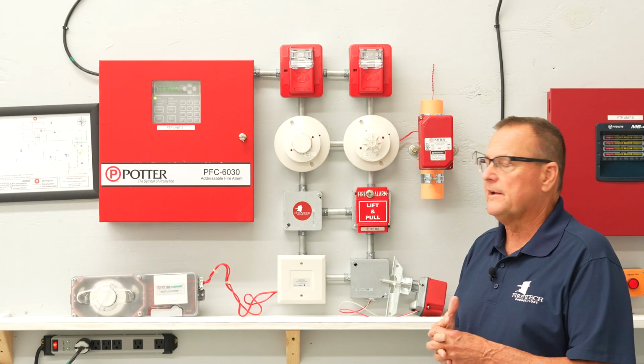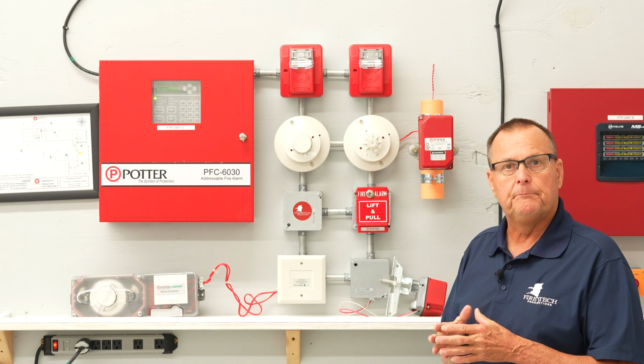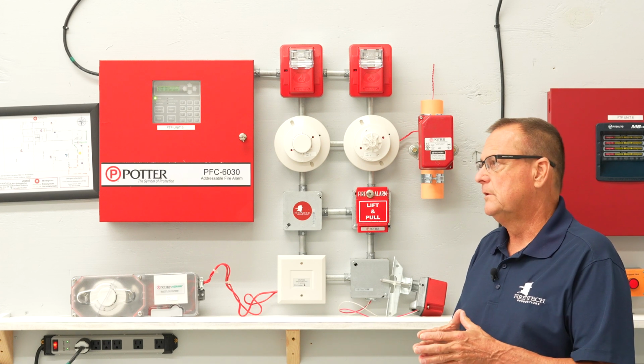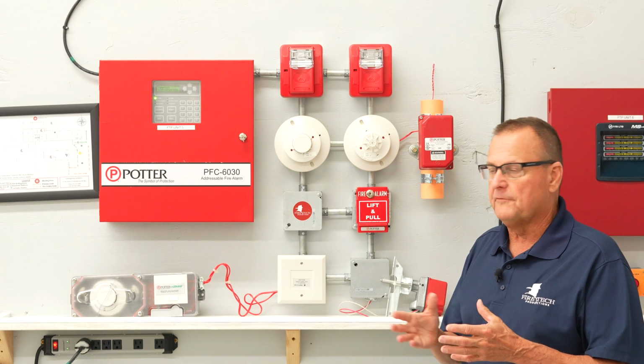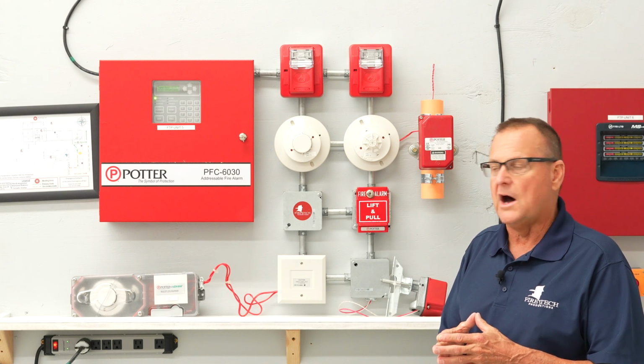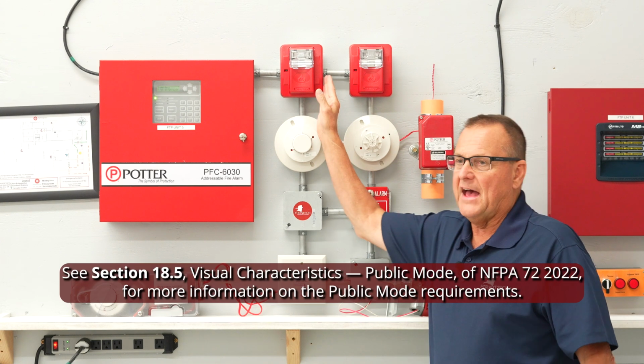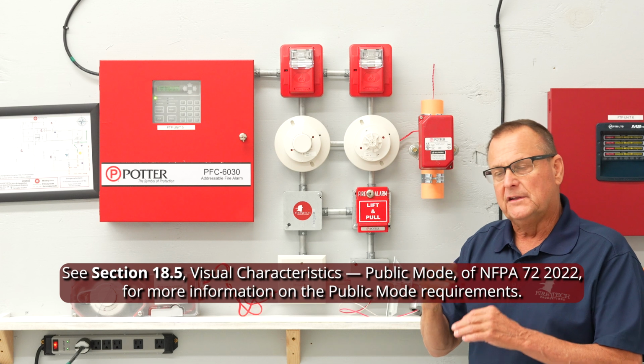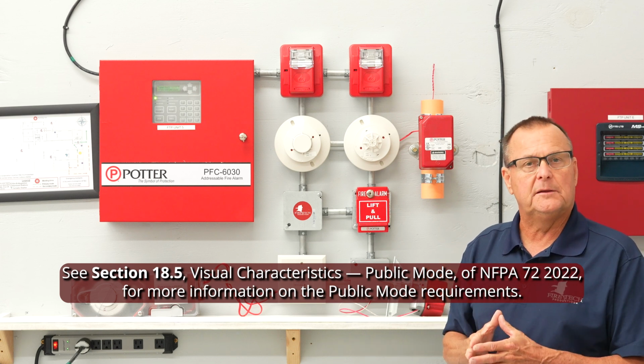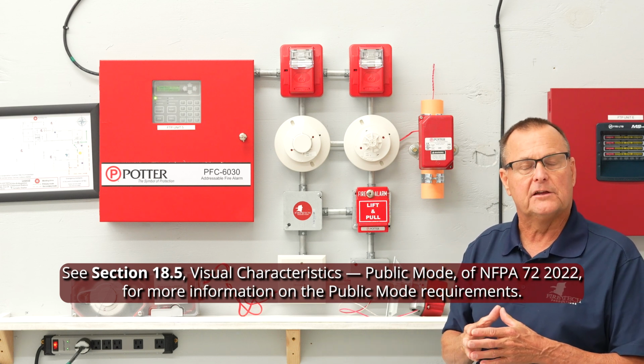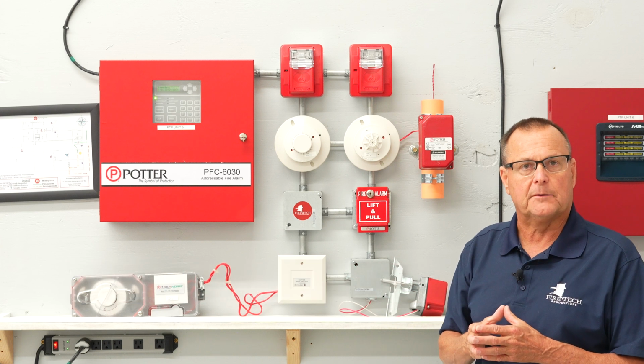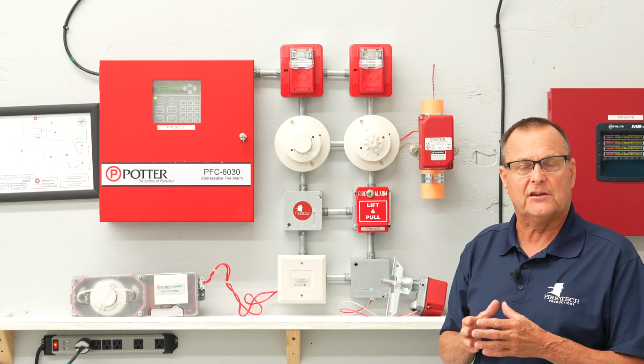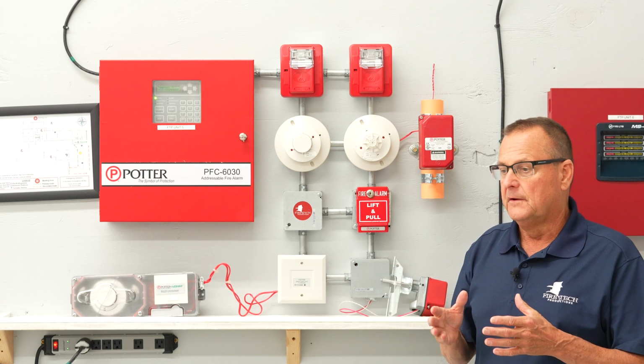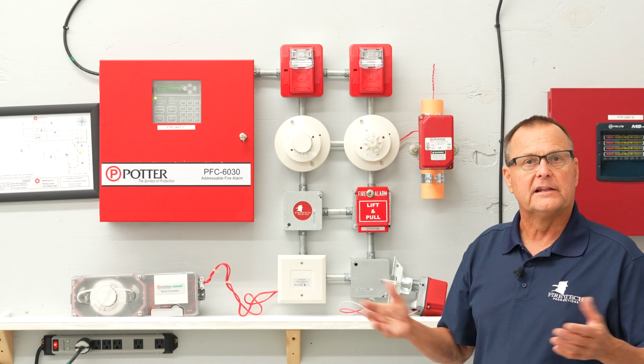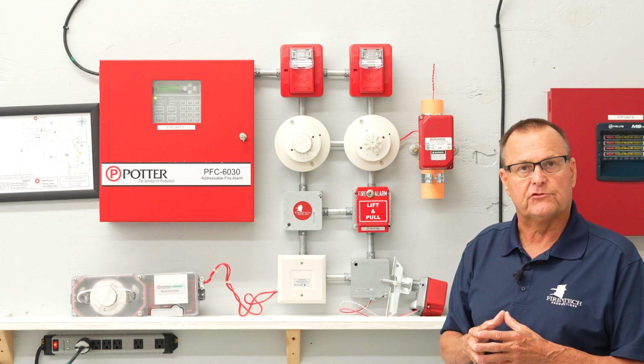Now, when we talk about NFPA, we talk about both the public mode and private mode. The public mode is the more prevalent mode that we see in commercial occupancies, and the intent is that the noise levels need to rise at least 15 dBA above the average ambient noise present in that occupancy. We're intending to evacuate the building, causing people to exit and leave the building during the emergency condition.